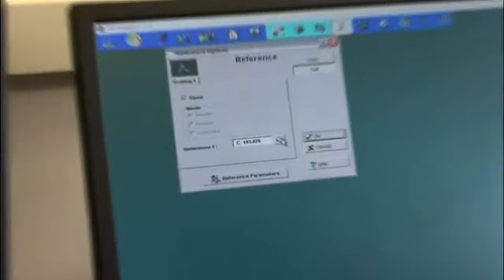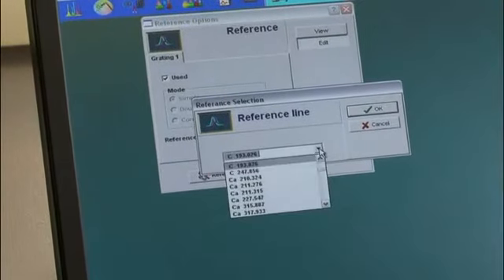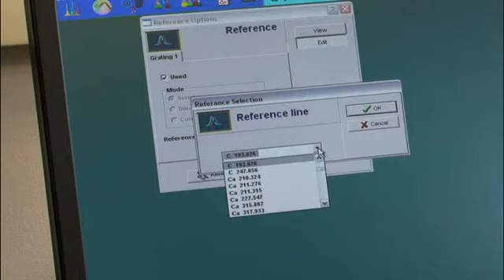Over here is where you set your reference. It allows you to pick whatever you want to use as a reference. But again, that always has to be in the plasma because if you do a peak search or a calibration or an analysis, it's always going to go back and look at the reference, which is this carbon line.